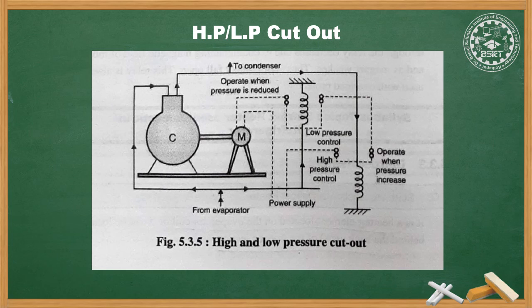The cyclic control operated by changes in suction pressure can be utilized to control the temperature in the space. The possibility of suction pressure becoming considerably low is due to a sudden reduction of load on the refrigeration system. The low pressure control protects against extreme compression ratio, freezing of the evaporator and leakage of air in the system. In actual practice, low and high pressure controls operate simultaneously.